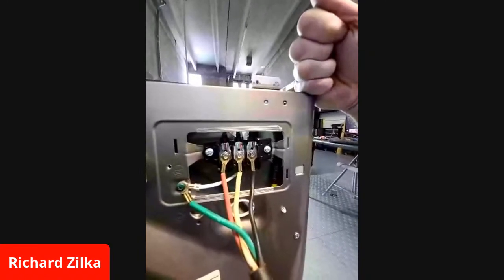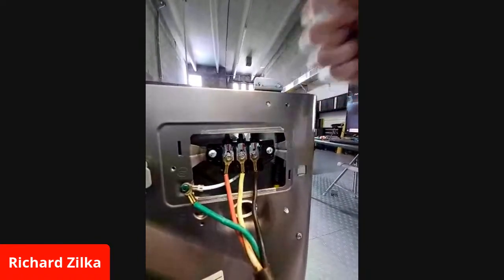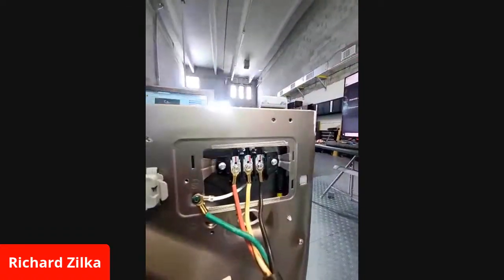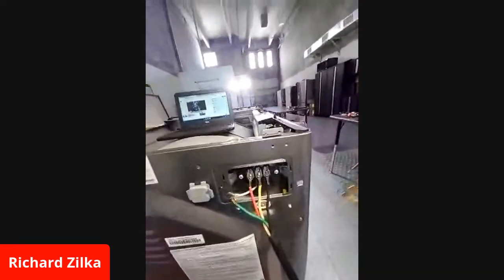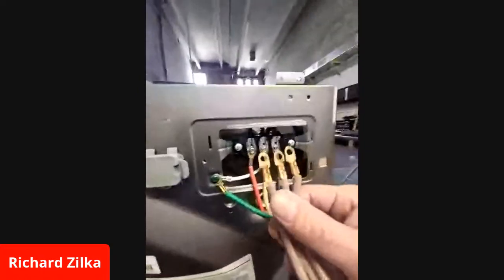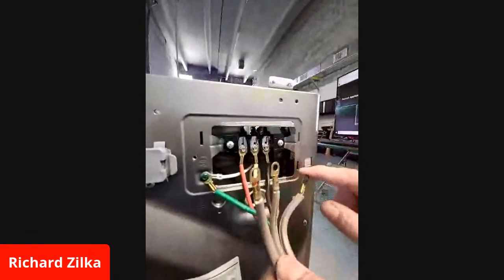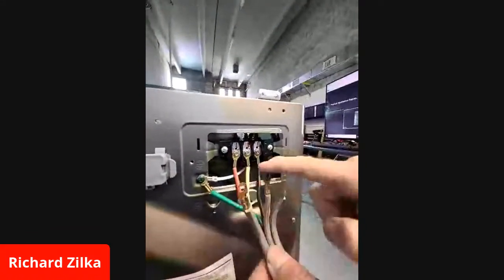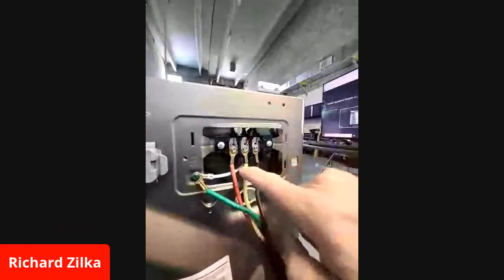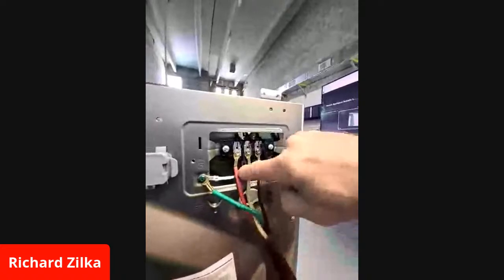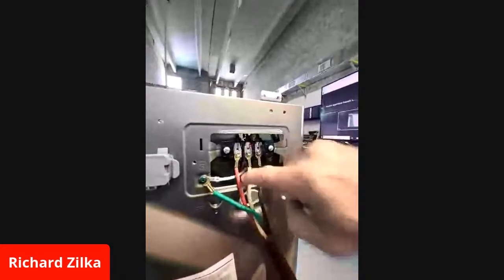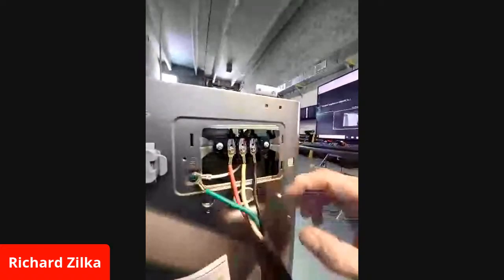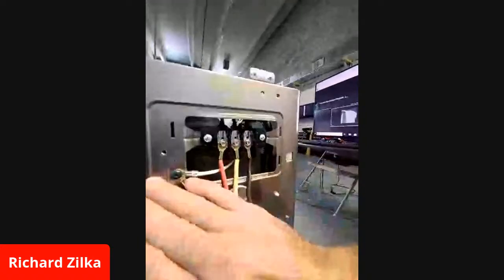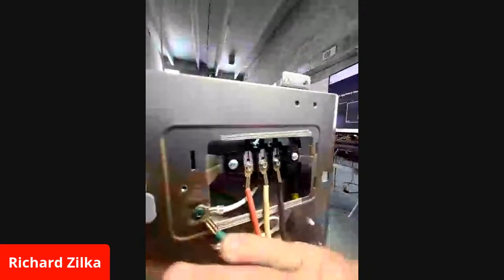Go ahead and dive into it. Expose the problem. I'm not going to unplug the machine, so I'm not messing with the line. When you have a 3-wire cord that only has 3 wires, one is line 1, one is line 2, one is neutral. They use neutral here, this white wire, as a ground because the 3-wire cord doesn't have a ground wire attached to it.